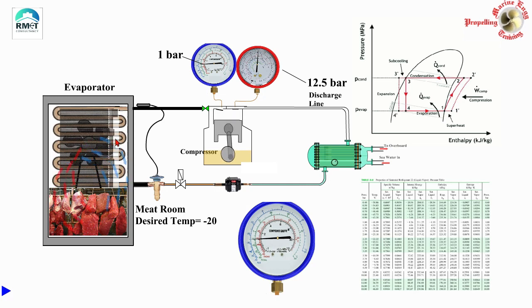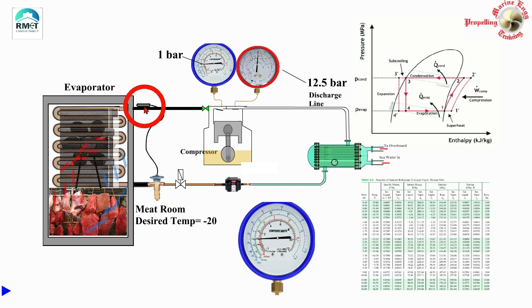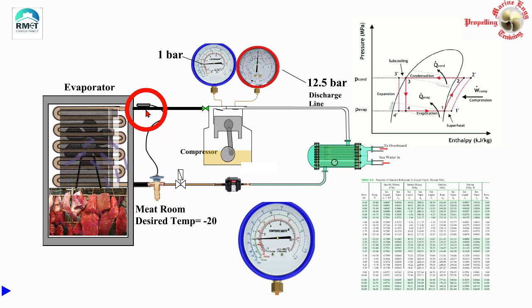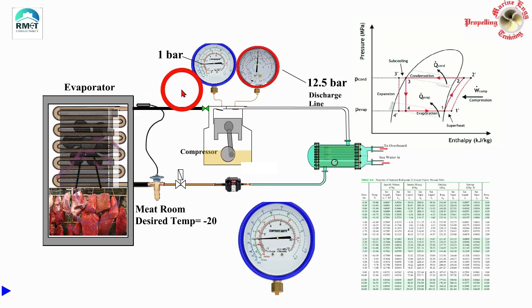By the time the refrigerant comes near the exit of the evaporator, we expect that the liquid freon should be completely converted to gas, and in the last part of the evaporator the gas should actually be heating up. So we expect that when the refrigerant gas is leaving the evaporator, it should be in a superheated state. This is controlled by the expansion valve, which gets inputs from a bulb attached to the return line pipe going to the compressor suction. This bulb ensures that the refrigerant gas leaving the evaporator is in a superheated state.